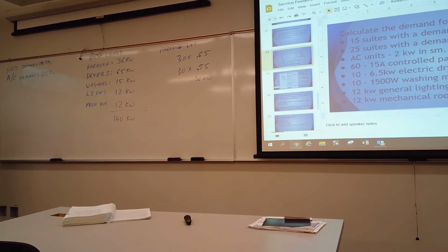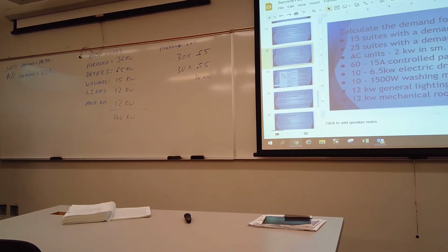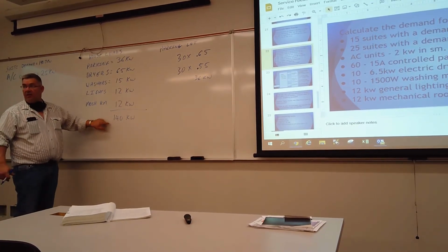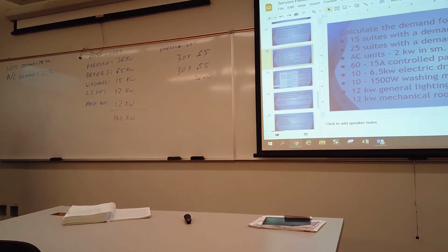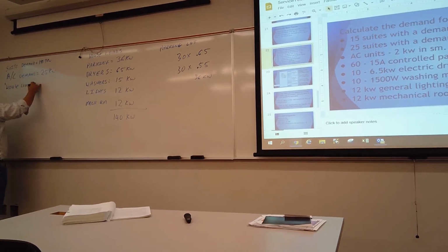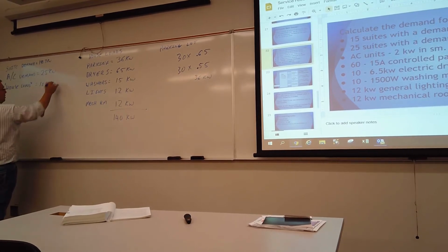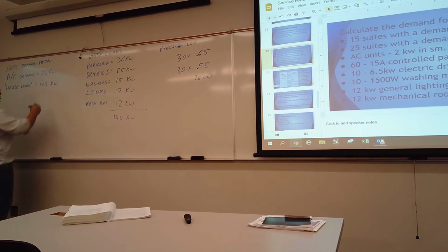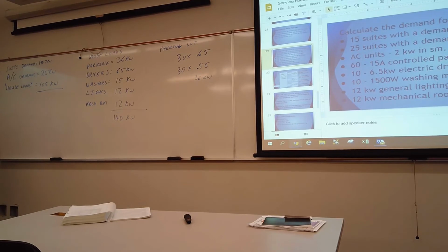That's our house demand, and then it says we can take the total of that and add it at 75% towards our main service. Keep this number written down because it's going to be important in a minute. So 140 times 75% is 105. So our total demand for this apartment building, 140.7 plus 25 plus 105, 270.7.